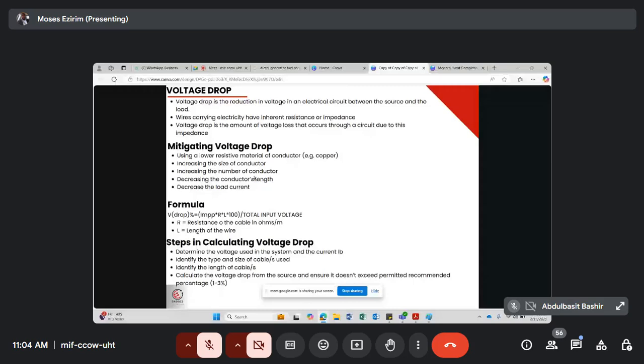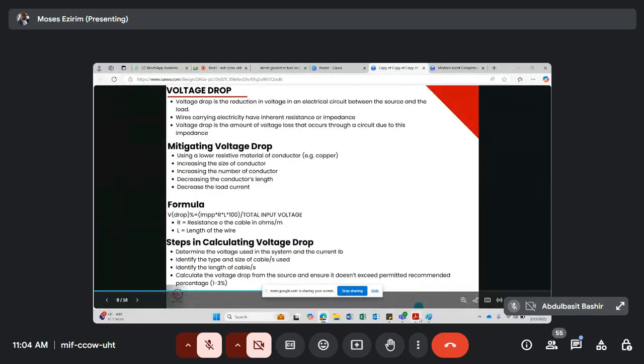So now, what is the formula for calculating voltage drop? This is the formula here: IMP times the resistance times the length times 100, divided by the total voltage. The resistance is the cable's resistance in ohms, while L is the length of the wire. The total voltage, I'm sure you know, for example the cable.